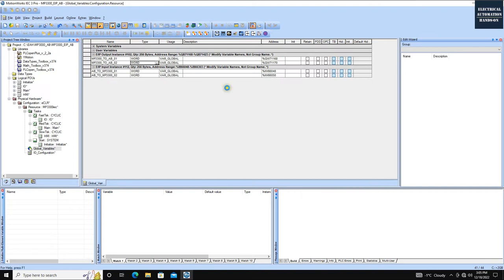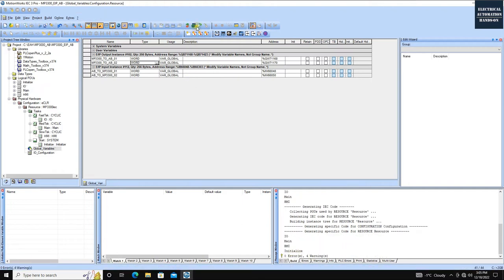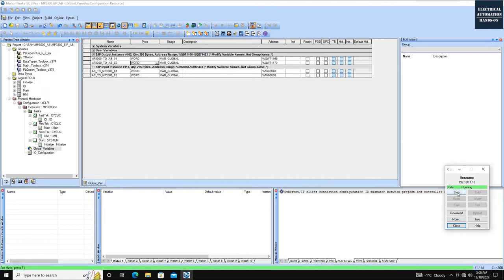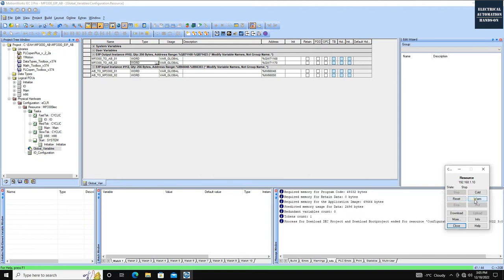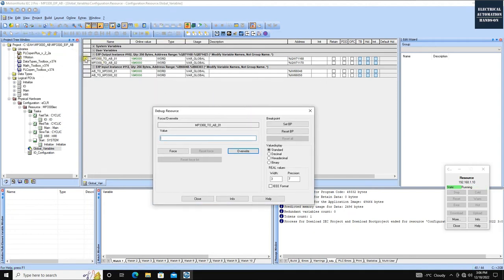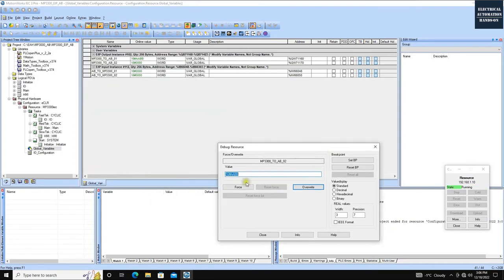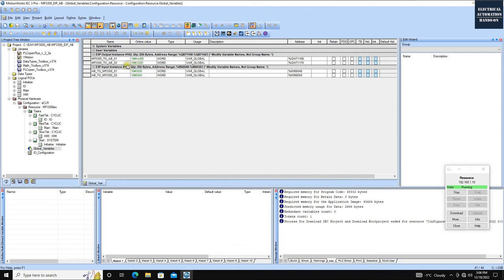We've configured two words for each direction. Now save and compile the project. It compiled with no errors. Stop the controller and download. Click Download and then Warm Start. The controller starts. Click Debug On to monitor the outputs. In the output variables, let's prepare some test data. Double-click and write the hex value 0xAABB for the first word, and 0xCCDD for the second word. Once Allen-Bradley sets up communication successfully, we should immediately see this data on their side.